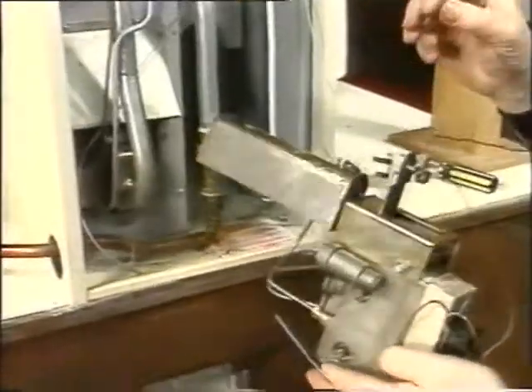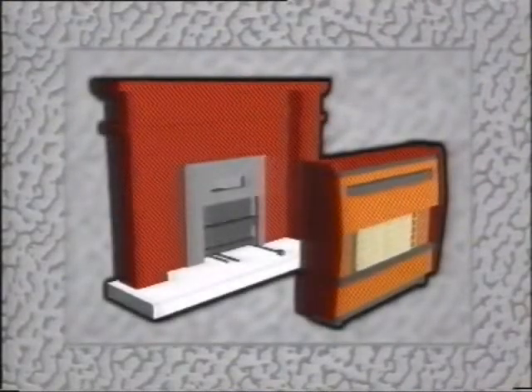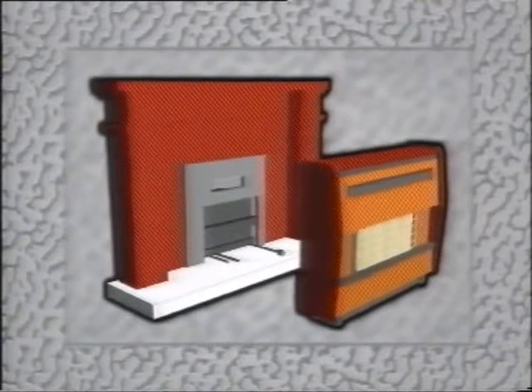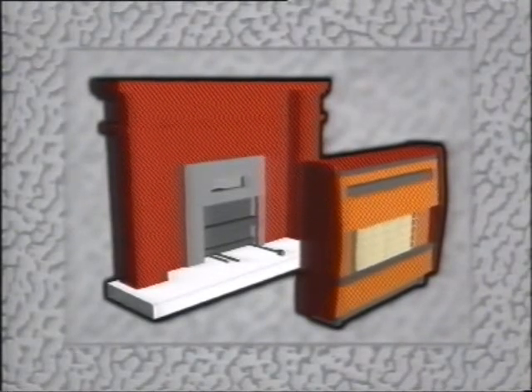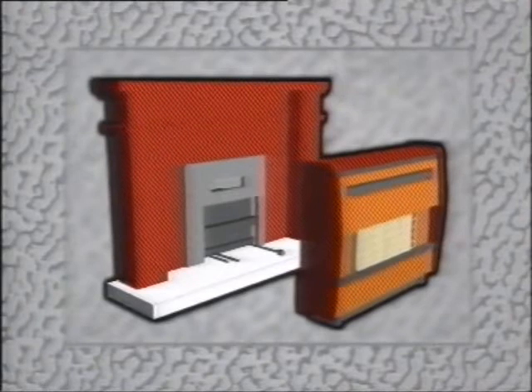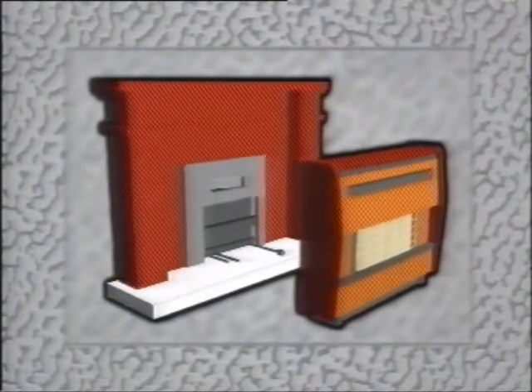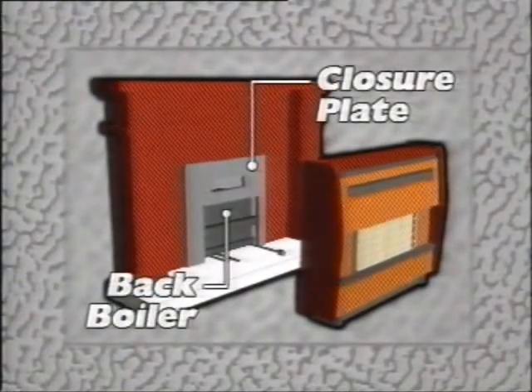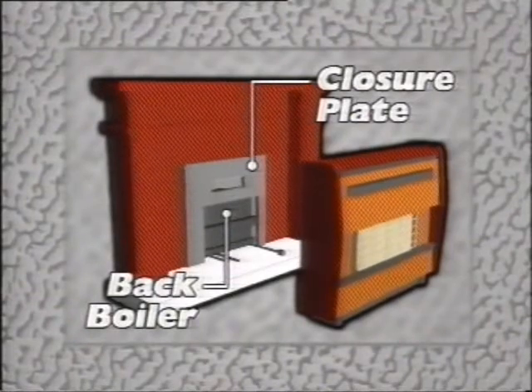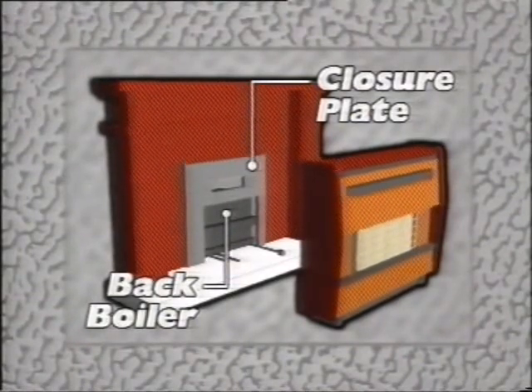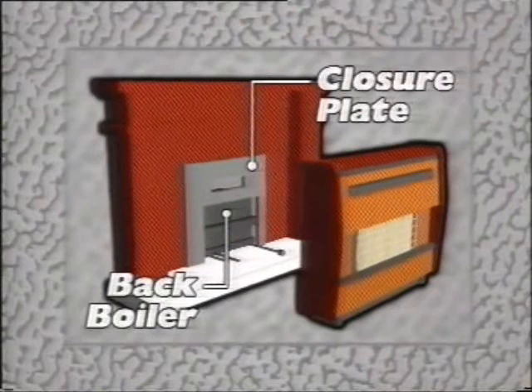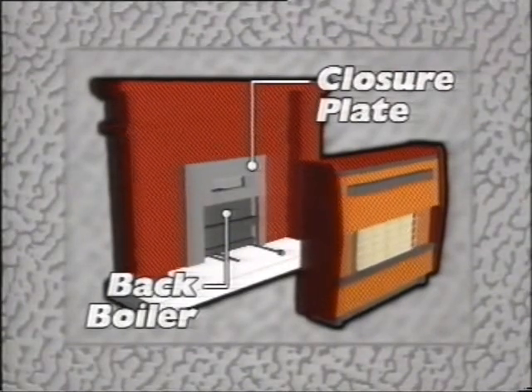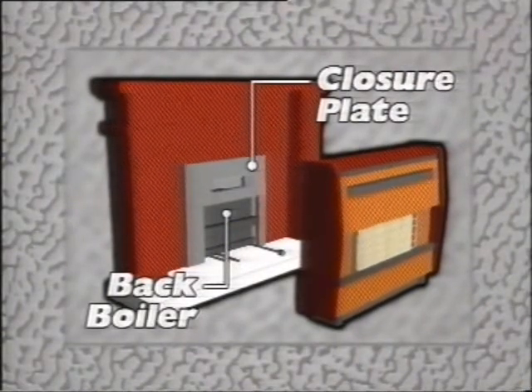The back boiler is fitted into a fireplace, so before you install it, you have to check the chimney. There must be no problems with downdrafts. It has to be swept and high enough to meet the manufacturer's requirements. It's important, too, that the flue is big enough to cope with the maximum combined ratings of a fire and back boiler unit. Finally, any pipework in the fireplace recess has to be wrapped with a protective coating to avoid corrosion.